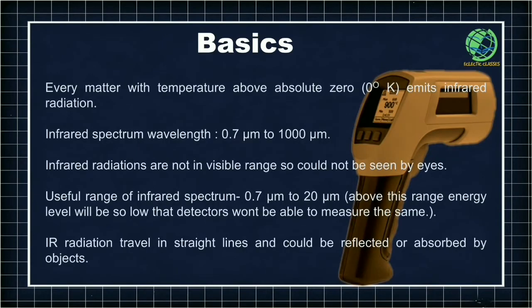So let us start with the basics. Any object which is above the absolute zero temperature — that is zero degrees Kelvin — will always emit infrared radiation. The infrared radiation spectrum wavelength ranges from 0.7 micrometer to 1000 micrometer. However, for infrared thermometers we use only 0.7 micrometer to 20 micrometer of that spectrum, as any radiation above this range results in a very low energy level — so low that detectors cannot measure it.